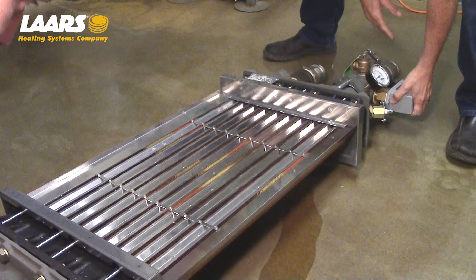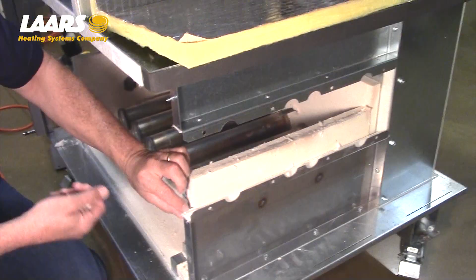On the top, we have V-baffles that are in position. You can take out these cross members and remove the V-baffles so you can also get in clean in between the fins. Inspect the gasket material and again your refractory block. If needed, you want to replace this block.